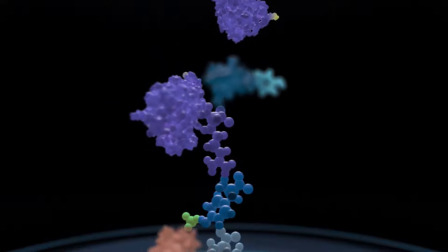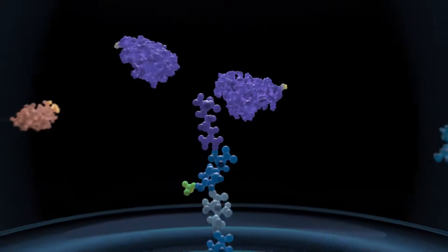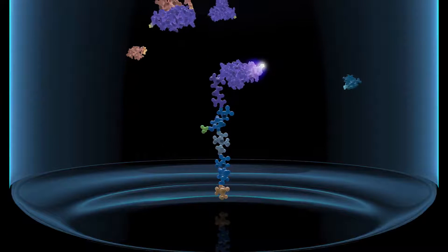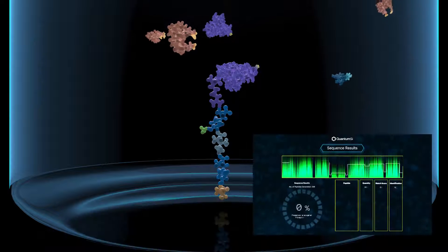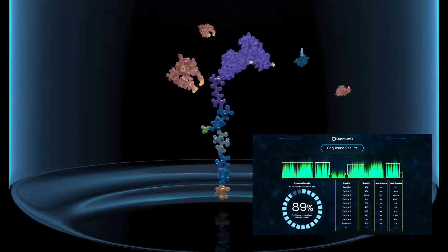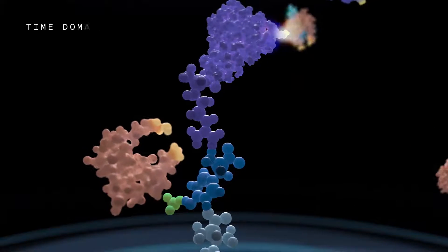Signal is generated by fluorescence, as each well provides a reaction chamber and a single molecule detection system. Pulse light stimulates the fluorescent molecule to emit a photon. A sensor measures the number of emitted photons and their time of arrival to compute the fluorescence lifetime instead of color. This is called time domain sequencing.